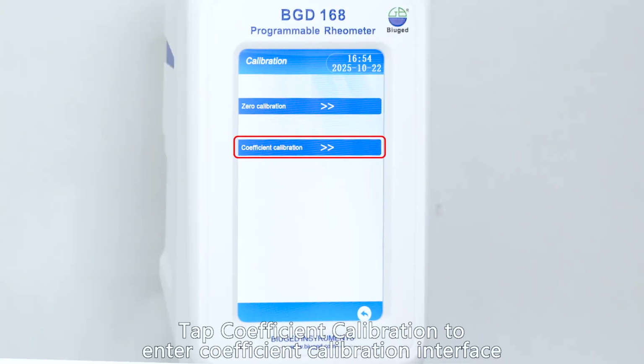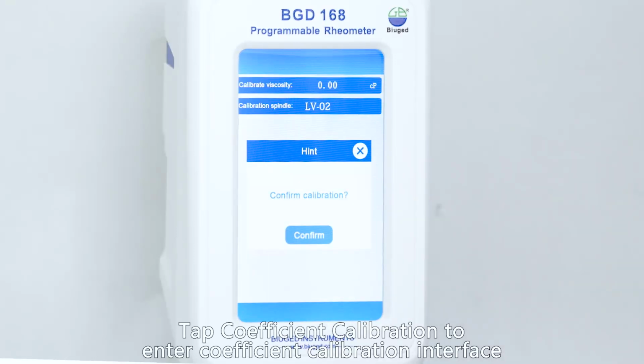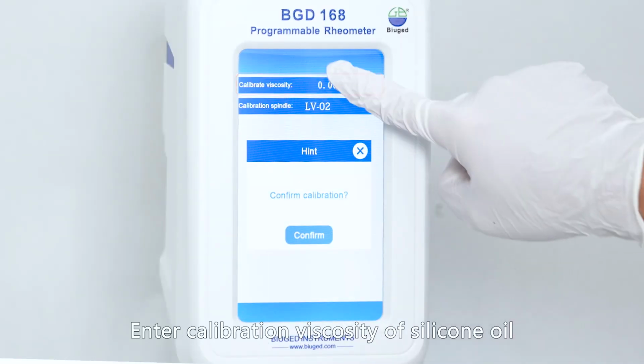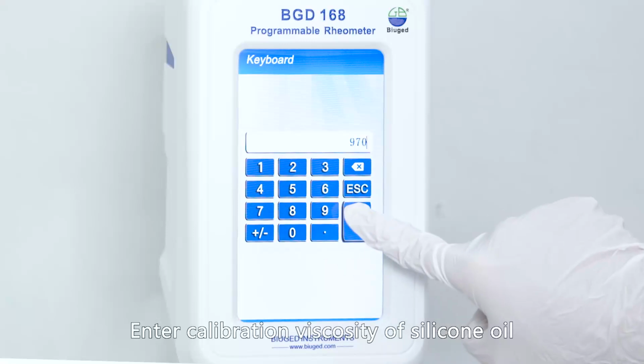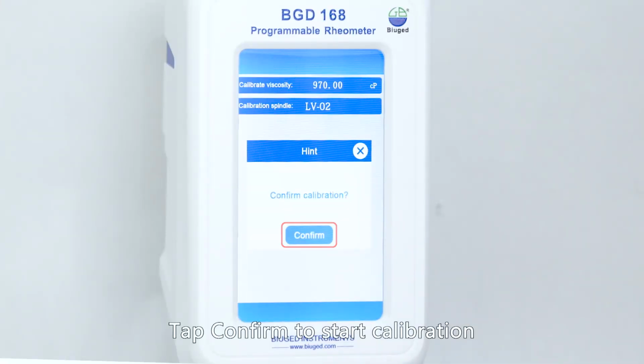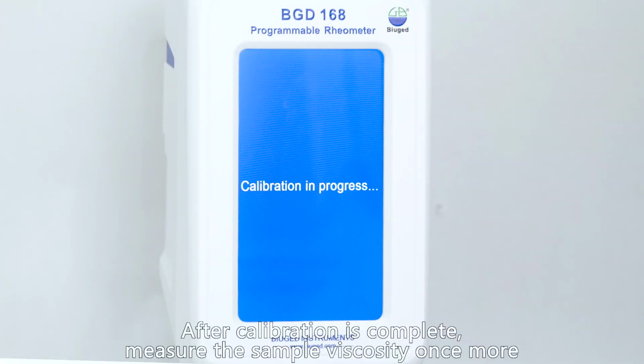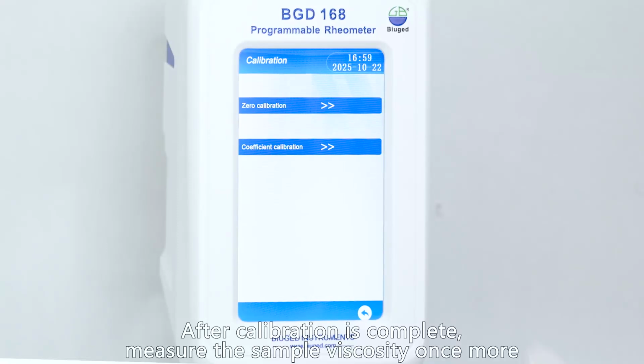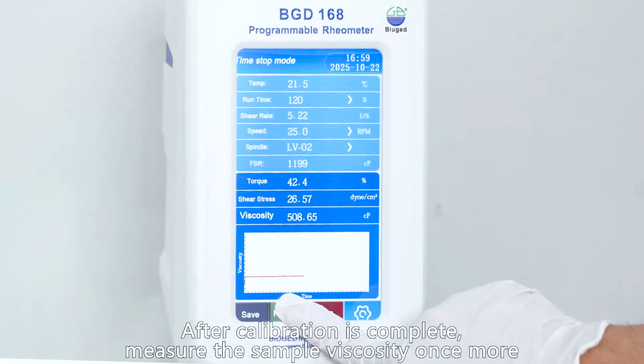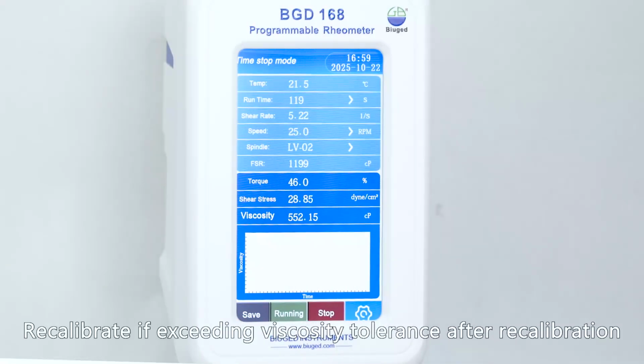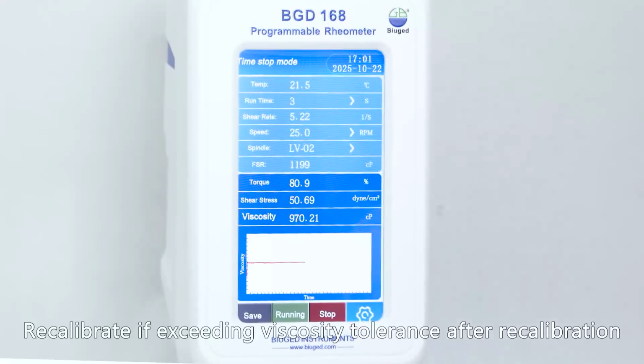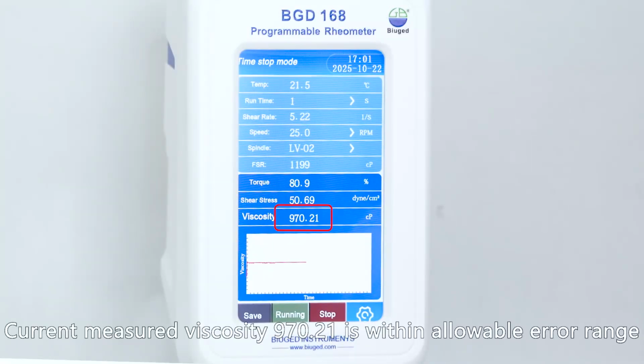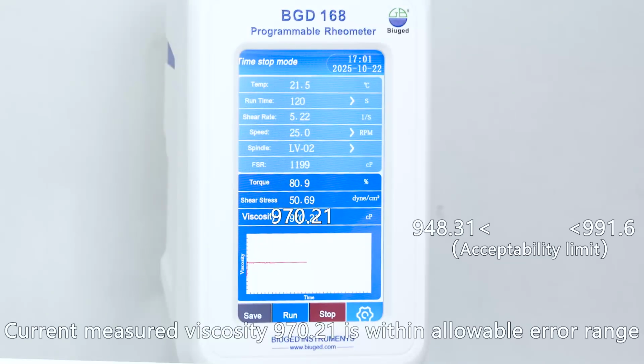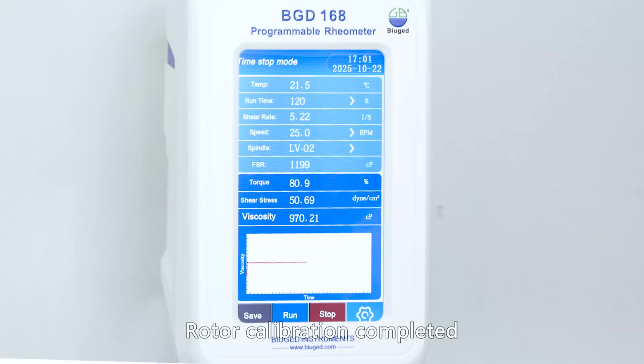Tap coefficient calibration to enter coefficient calibration interface. Enter calibration viscosity of silicone oil. Tap confirm to start calibration. After calibration is complete, measure the sample viscosity once more. Recalibrate if exceeding viscosity tolerance after recalibration. Current measured viscosity 970.21 is within allowable error range. Rotor calibration completed.